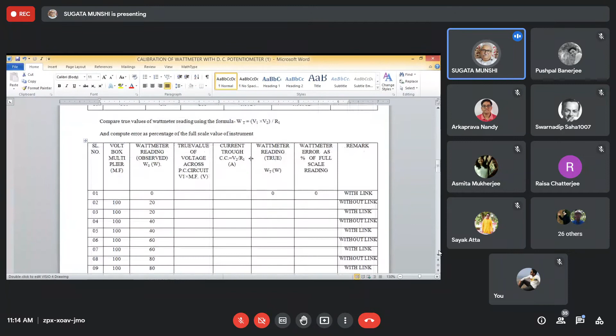Such a standard cell is connected to this potentiometer when the switch is in the standardized mode. So you obtain ET, that standard cell voltage at T degrees centigrade read from a thermometer. You adjust the position of this wiper part - say if it comes out as 1.0184 volt, you adjust the position of this wiper such that it is at the 1.0184 volt mark. So when that is the case, now what do you do?